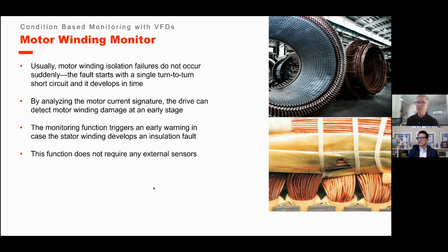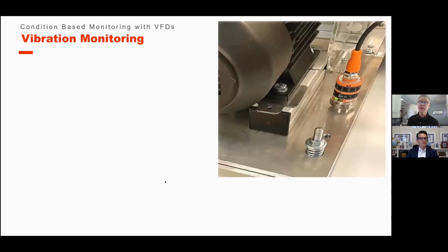That's very unique. Once a drive sends the warning or the alarm, it can send it various ways. It can show it on a keypad. It can show it on a communication bus network. If you have Ethernet, Profinet, any bus network, pretty much cover them all these days. Everybody does. You can send it that way. You can even tie it to a relay. Actually, it's not on a PowerPoint, but you can certainly tie a warning or an alarm to a relay in a drive, or 2 relays, or multiple relays, and give yourself hard IO warnings. So you can trigger the lights. You can do all different types of things. So there's a lot of information, a lot of avenues and communication paths, which is really handy to have. The second monitoring value that I want to talk about, remember there were 3, is vibration.